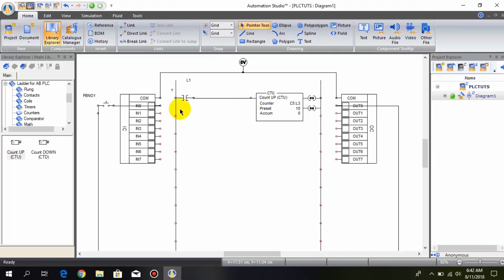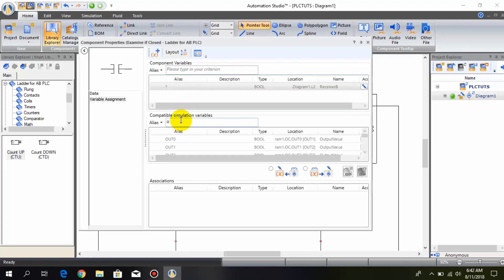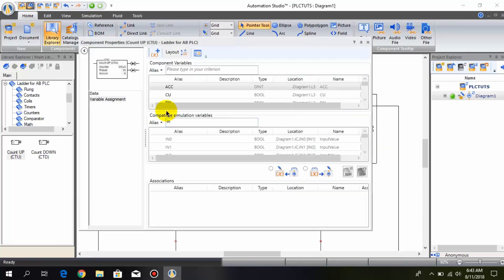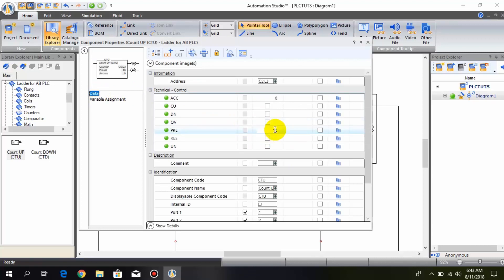I connect this counter with input 0. Now we will change the preset of this counter to 4, because we have to turn on the DN bit when it counts 4, so I change its preset from 10 to 4.